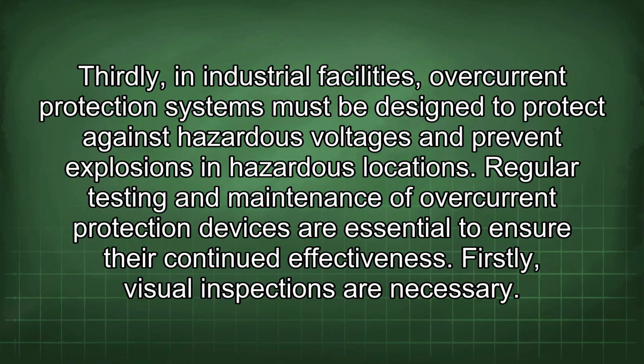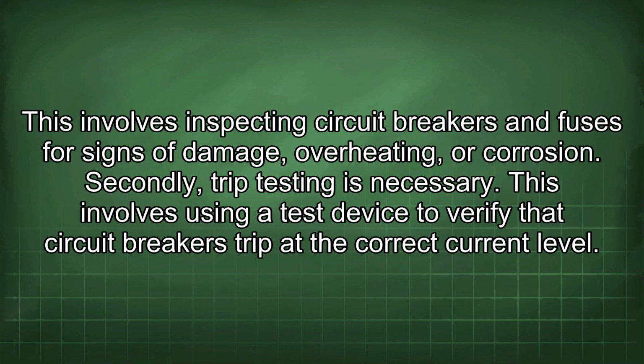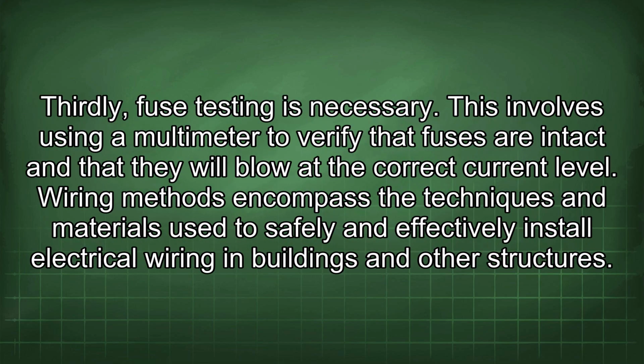Firstly, visual inspections are necessary. This involves inspecting circuit breakers and fuses for signs of damage, overheating, or corrosion. Secondly, trip testing is necessary. This involves using a test device to verify that circuit breakers trip at the correct current level. Thirdly, fuse testing is necessary. This involves using a multimeter to verify that fuses are intact and that they will blow at the correct current level.